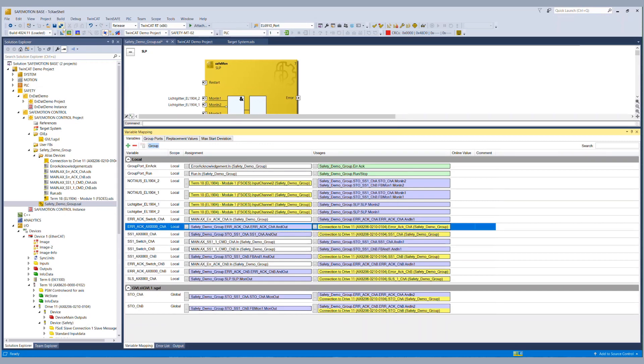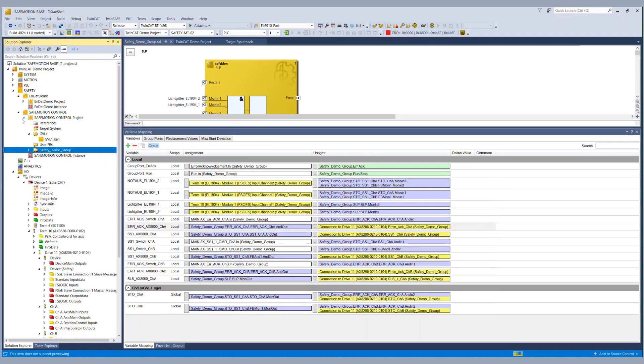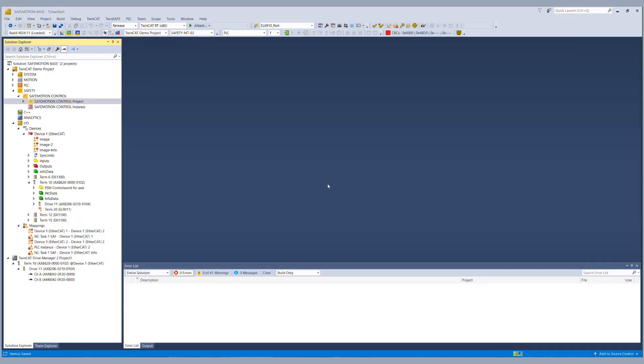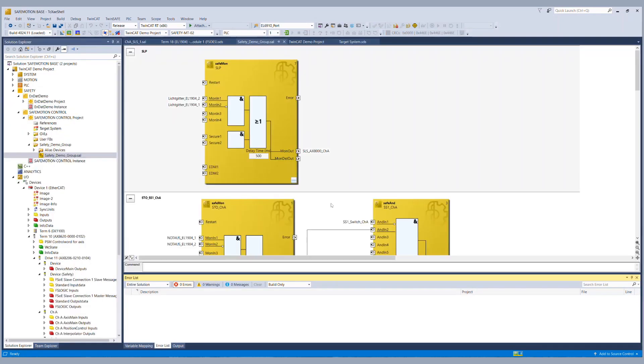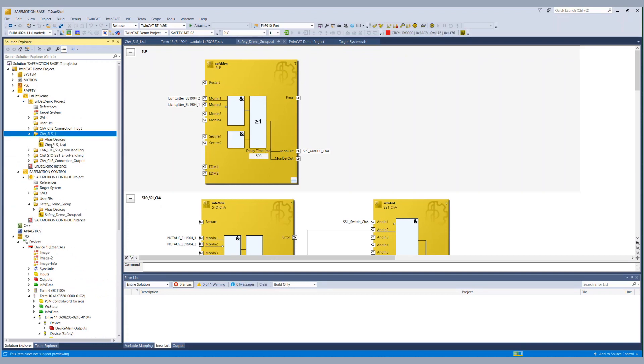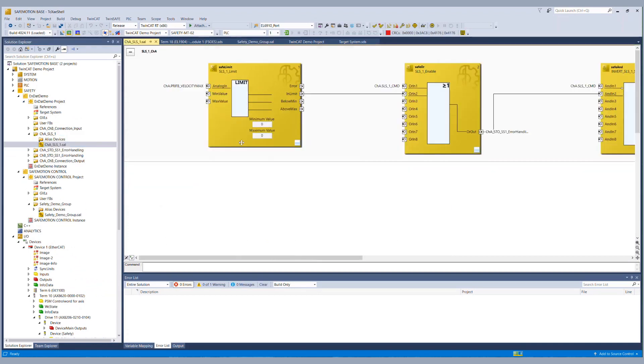So basically that was all for the generation of the safety functionality. The last step we still have to do of course is to configure our SLS functionality. To do that we go to the AX8000 safety project to the corresponding TwinSafe group for SLS1 and we have a safe limit function block where we configure our pre-calculated values.